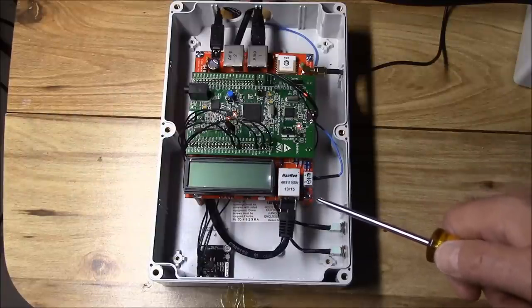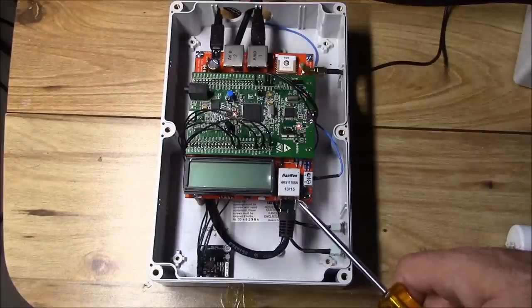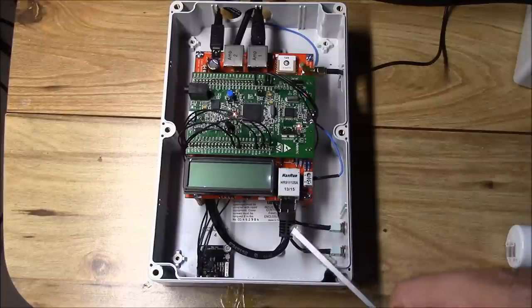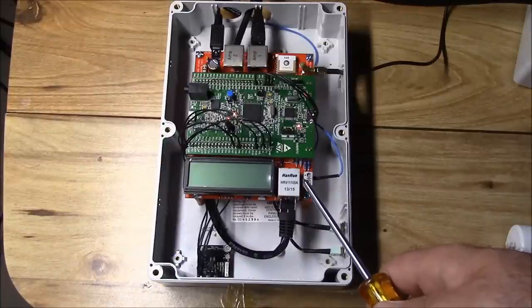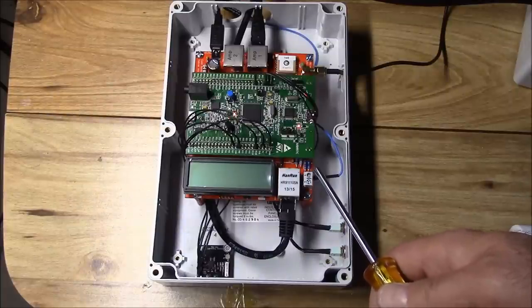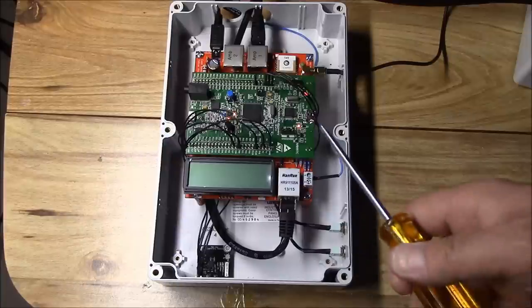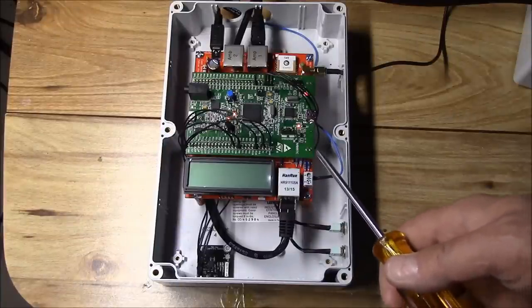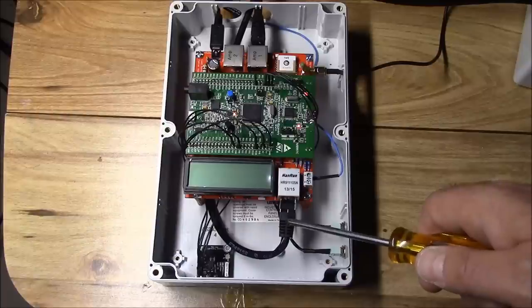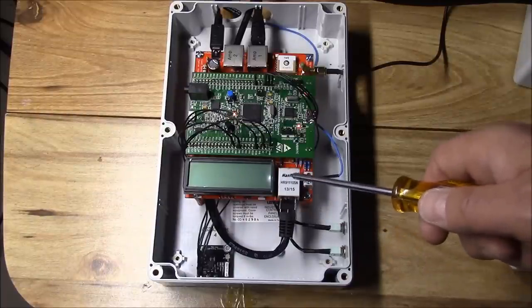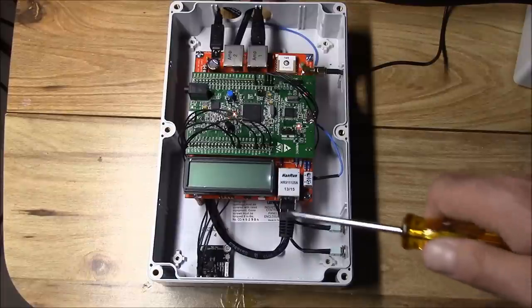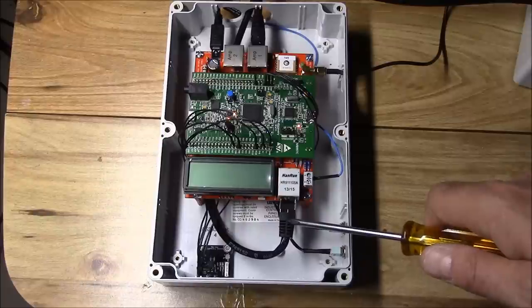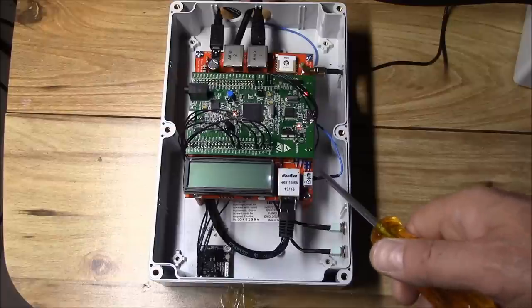We've got a networking connector here that handles the interface to the ethernet router. Finally here we have a ground terminal connector. It is very important that the system be grounded to at least the center screw of the power outlet. An ideal ground would be a cold water pipe ground or some other suitable ground arrangement. Now one thing to look out for is that right now there's a shielded ground cable being used to connect this networking connection back to the router. If you've got a shielded socket on the router that the other end plugs into, you may have a ground path going through the shield.